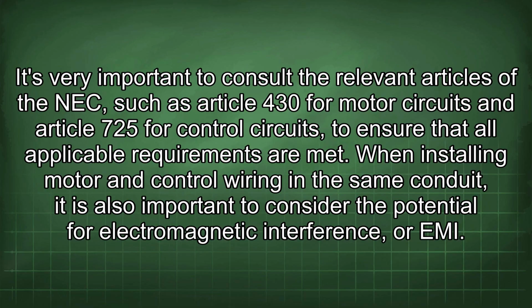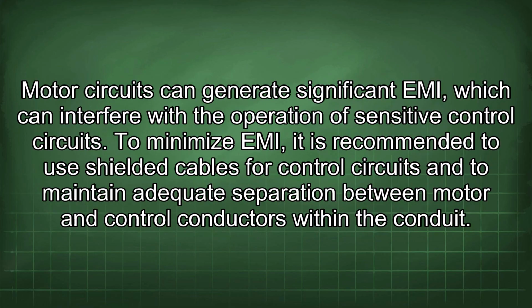It's very important to consult the relevant articles of the NEC, such as Article 430 for motor circuits and Article 725 for control circuits, to ensure that all applicable requirements are met. When installing motor and control wiring in the same conduit, it is also important to consider the potential for electromagnetic interference, or EMI. Motor circuits can generate significant EMI, which can interfere with the operation of sensitive control circuits. To minimize EMI, it is recommended to use shielded cables for control circuits and to maintain adequate separation between motor and control conductors within the conduit.